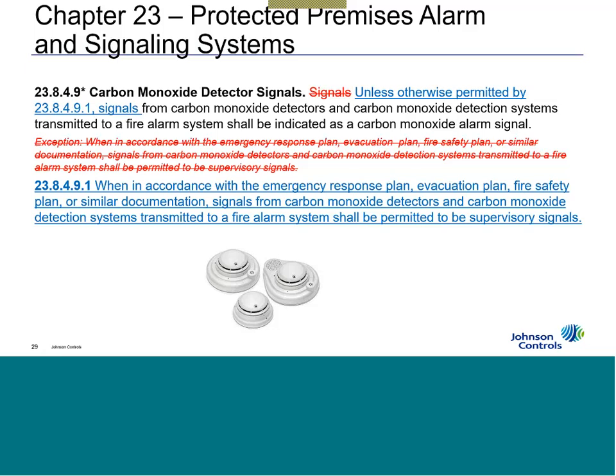So if you have, for example, a Simplex or an Autocall system, and you have the LEDs on the side and you have the function switches on the side, you can designate one of those to light up and indicate a carbon monoxide system has been activated, a detector has been activated. That meets the requirements of the code. So although we still have priority 1 or fire alarm, we have supervisory, you have trouble, you can have the extra one on the side.